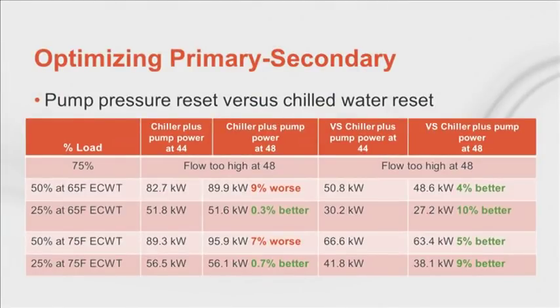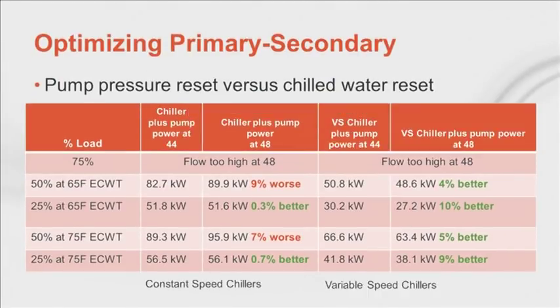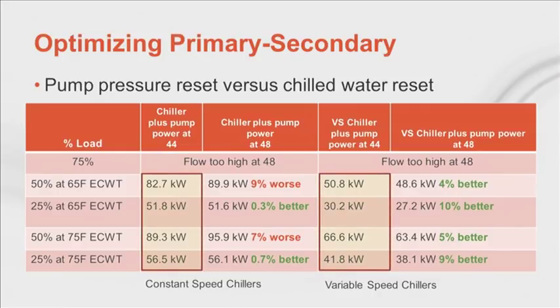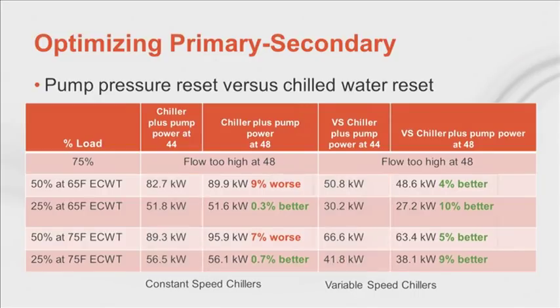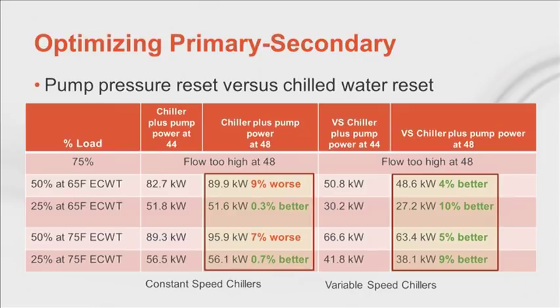Here's the brute force method, using chiller performance data and coil selections. For the base case, I assumed pump pressure optimization followed the affinity laws with some system losses. For the reset temperature alternative, I used 48 instead of 44 degrees, with two options for condensing temperature, 75 or 65. I calculated the required flow rate and pump energy at 75, 50, and 25% load. At 75% load, the coil I had selected couldn't take 48-degree water and still meet the load. The flow went above 100%. But before we spend any more effort on figuring just how warm we could allow the water to be at 75% load, let's see if the other load points encourage us.